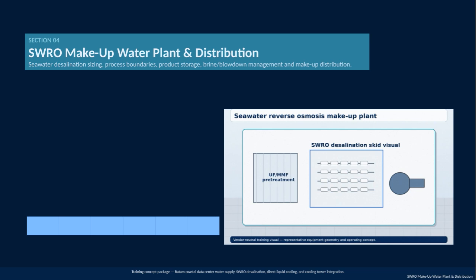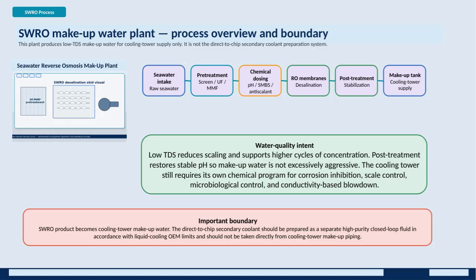Finally, we'll examine the distribution system that delivers this treated water as makeup water throughout the facility. This integrated approach ensures a reliable and sustainable water supply, critical for supporting direct liquid cooling and cooling tower operations at the data center. Here we're looking at the SWRO makeup water plant and its overall process.